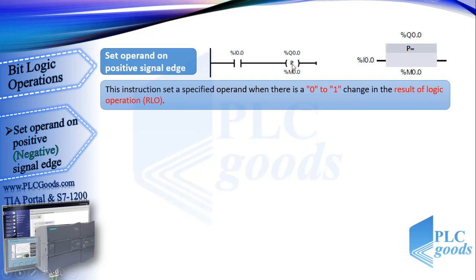This is like the previous instructions, but this instruction is used as an output. It sets a specified operand only for one program cycle when there is a 0 to 1 change in the result of logic operation RLO. See this simple program.